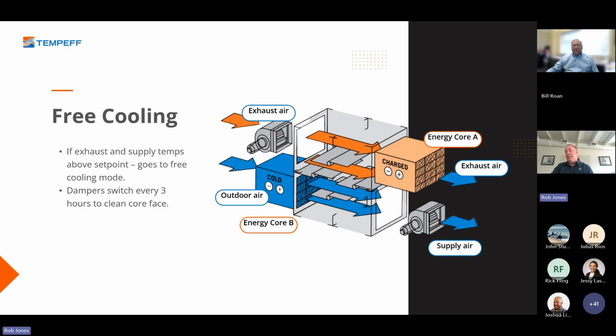Energy units can be too efficient, especially in the shoulder seasons. So we do offer, standard with all our units, a free cooling or bypass mode. This is where we stop energy recovery because the exhaust air set point and the supply air set point temperatures are above set point. So we no longer are required to do energy recovery. The exhaust air is just shot through the unit and out to the outside atmosphere, while the outdoor air is shot directly into the supply air.